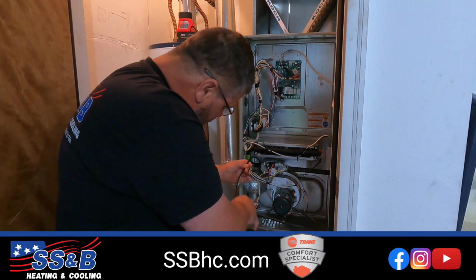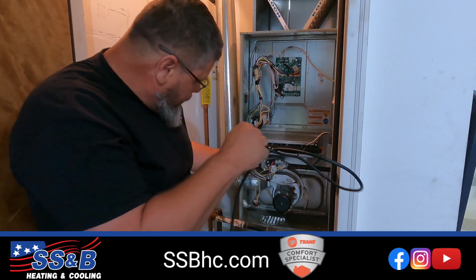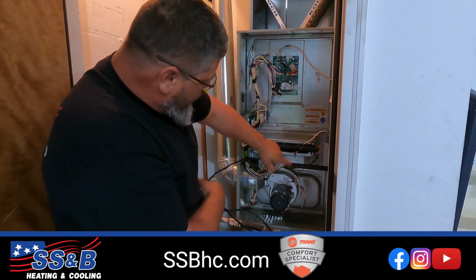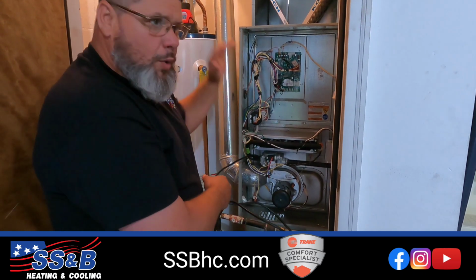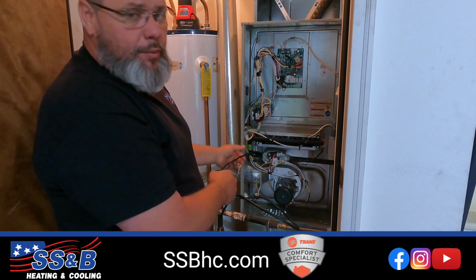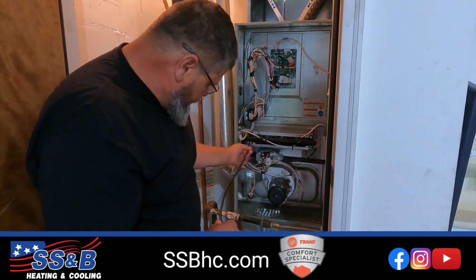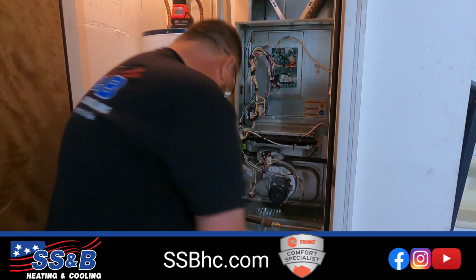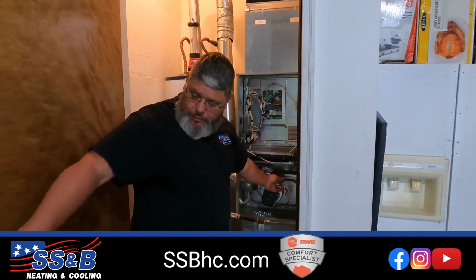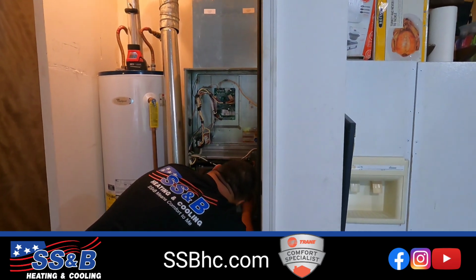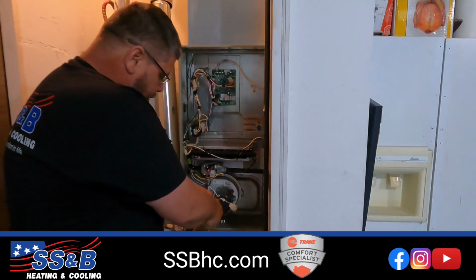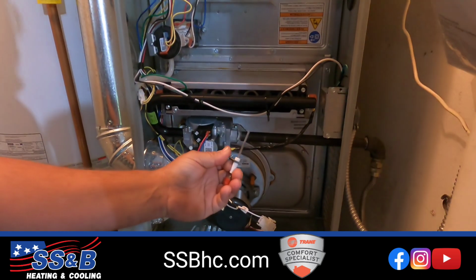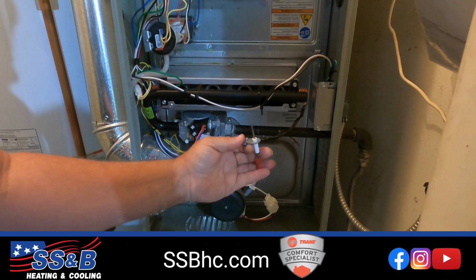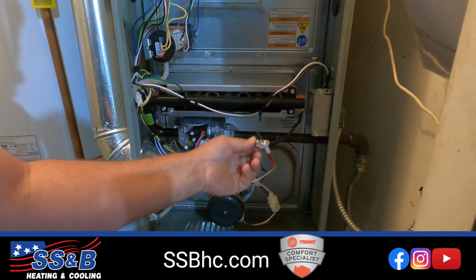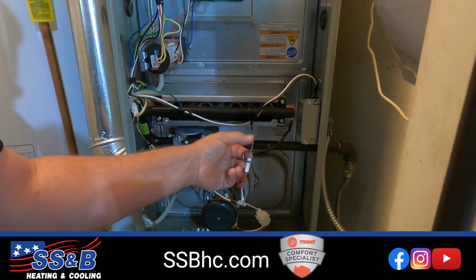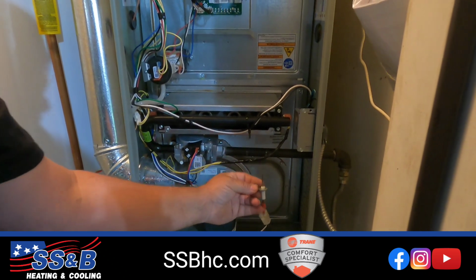It also allows us to gain access to the actual heat exchanger, which is where these burners are burning. That's your heat exchanger. Our scope allows us to go in there and check all those for cracks or holes or any problems that might exist in those. All right. Another thing that we always make sure is we always inspect and clean the flame sensor. So this is the flame sensor here. We always make sure to pull it out and visually inspect it and make sure that it is clean. This is probably one of the most common repairs on a furnace. If this isn't clean and reading correctly, the board will not allow the system to continue to run.